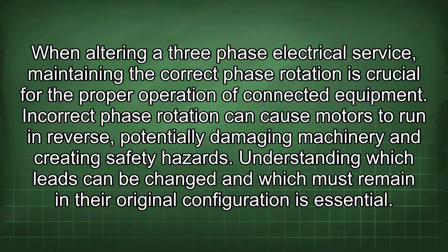When altering a three-phase electrical service, maintaining the correct phase rotation is crucial for the proper operation of connected equipment. Incorrect phase rotation can cause motors to run in reverse, potentially damaging machinery and creating safety hazards. Understanding which leads can be changed and which must remain in their original configuration is essential.